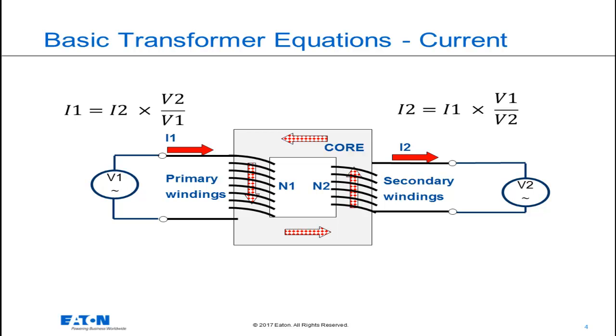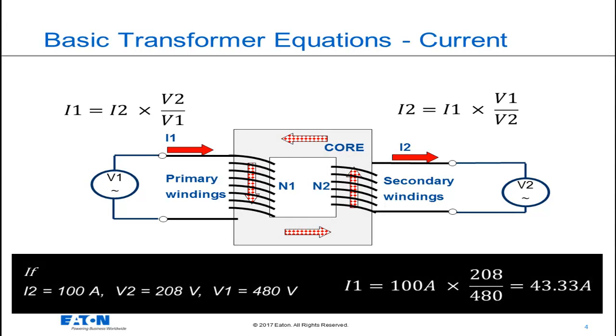To understand this, let's use an example. If we know the primary and secondary voltage of this transformer is 480 to 208 volts and we know the secondary current is 100 amps, we can calculate the primary current using the standard equation for I1. This shows that when this transformer is supplying 100 amp load, the primary current will only be 43.33 amps.